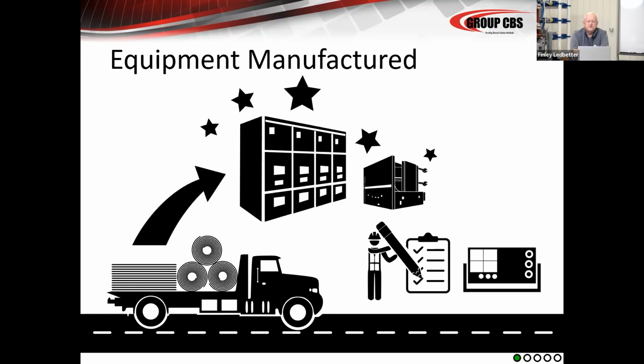The breakers are tested, normally open and closed about 300 times before you see them. If you ever look at the counter on a breaker, quite often the counter will say 9,996 or 9,992. That's because it came into the plant several hundred clicks before zero, and they intend to put enough operations on it to get it back to zero, but quite often they don't. So the equipment is manufactured. There's a certain amount of batch and quality assurance testing that goes on in the plants. And believe me, they all try to build a quality product.